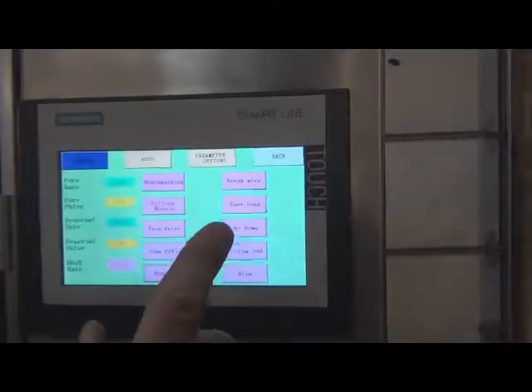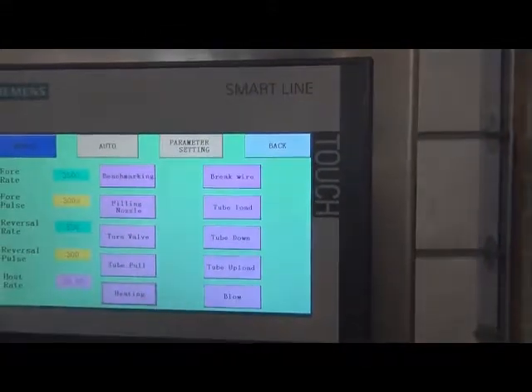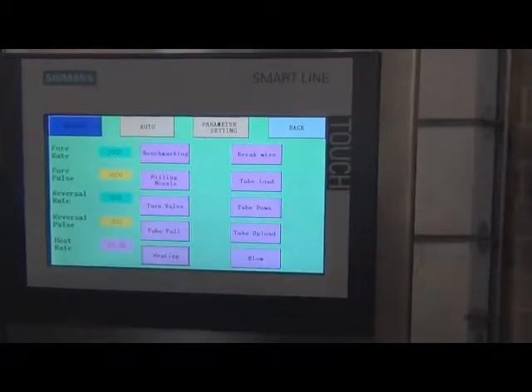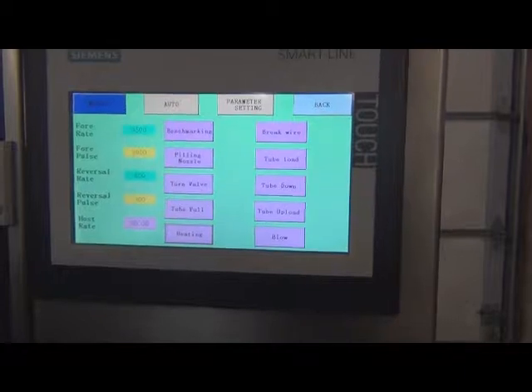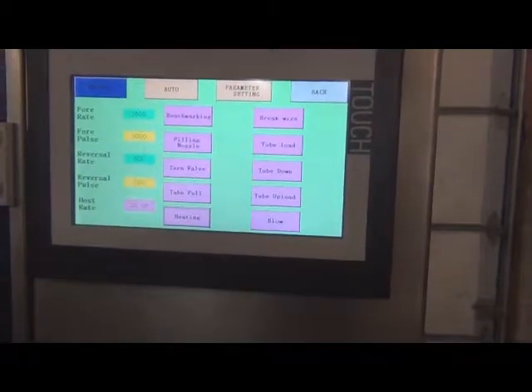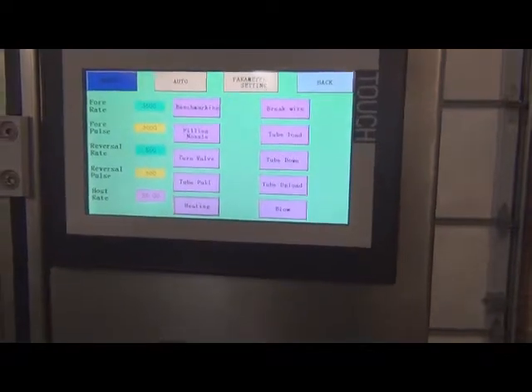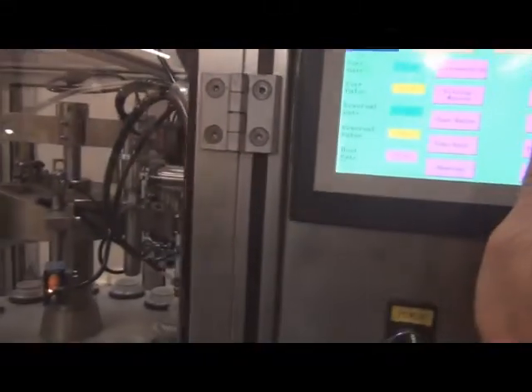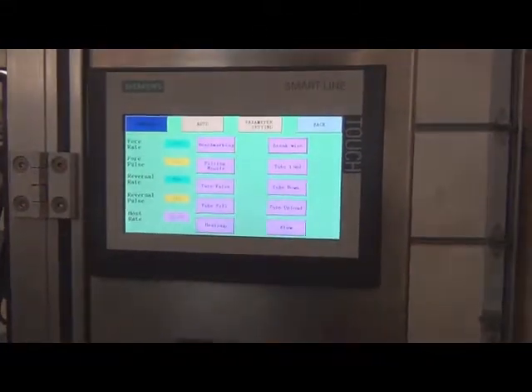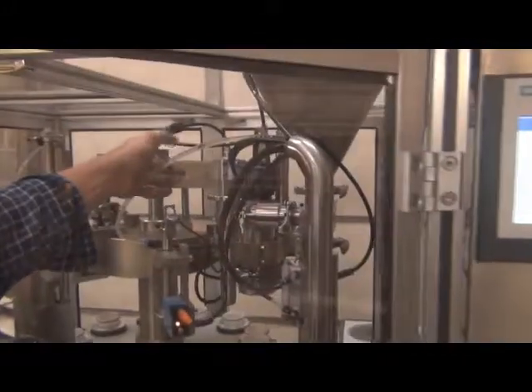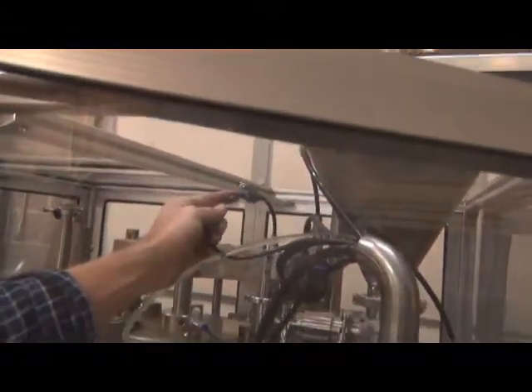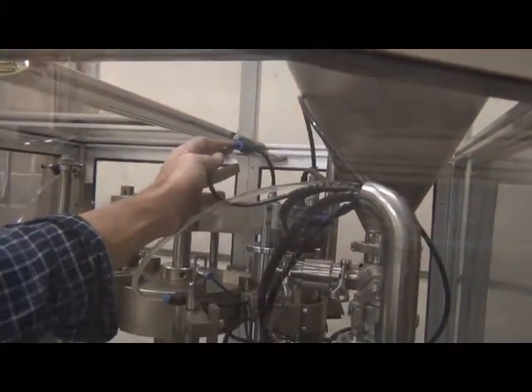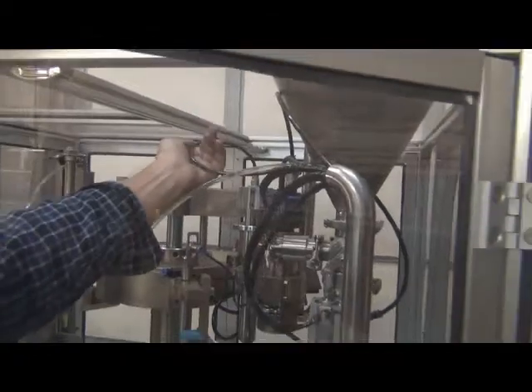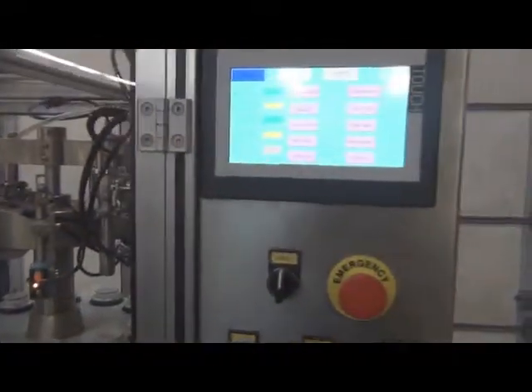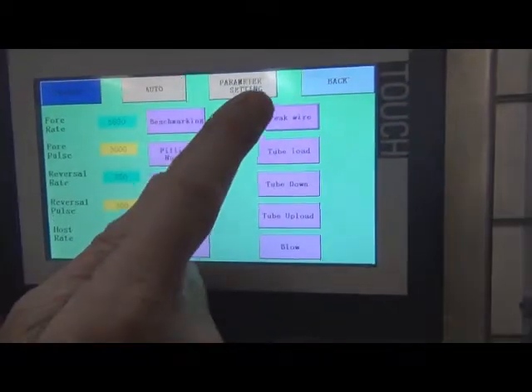Okay. Next thing was the break wire. That is a burst of air that comes down through the filling nozzle after the fill, and it is all timed in automatically, so that once it's done filling, it shoots a little bit of air through the nozzle and cuts off any stringing that may occur after the fill. Now I'll hit that and you can probably hear it. Hear it? Now that is controlled, by the way, through this. There's a flow control valve here. Can you see that? You can get more or less, depending on what is needed to break that string, by rotating that flow control valve to increase or decrease the force.